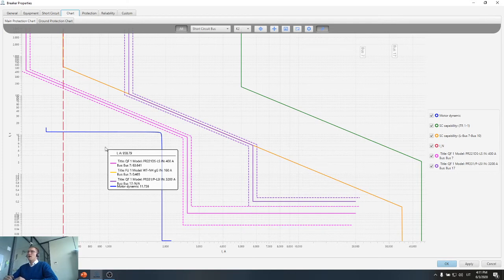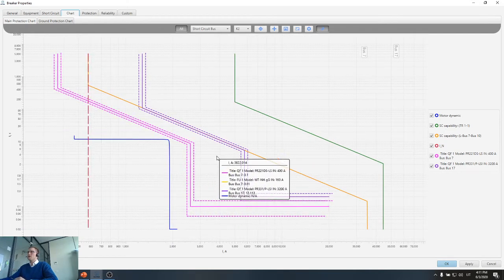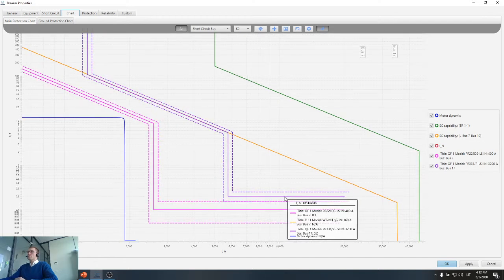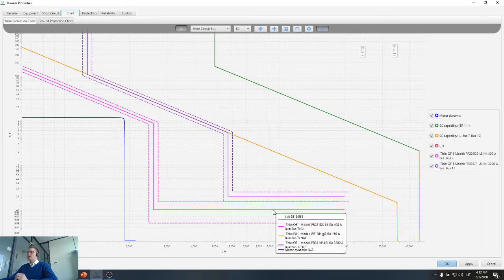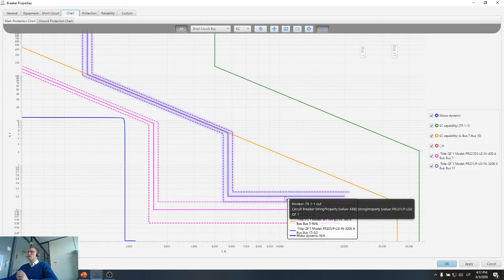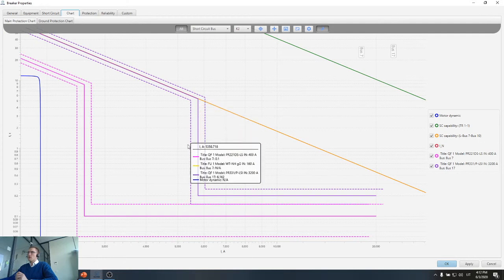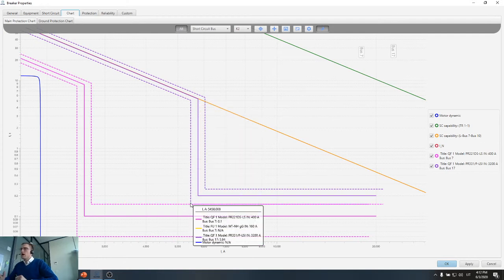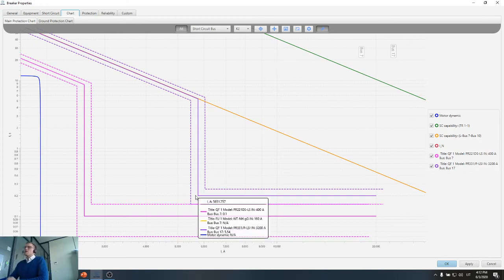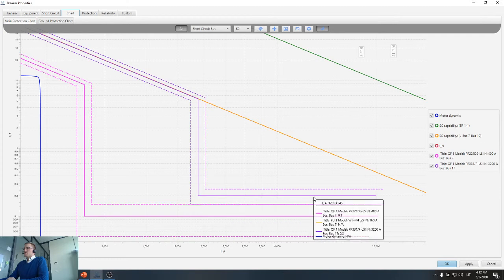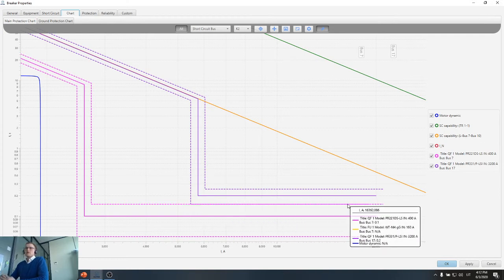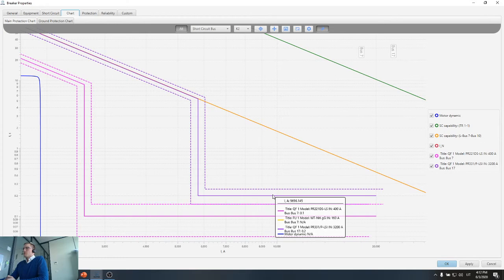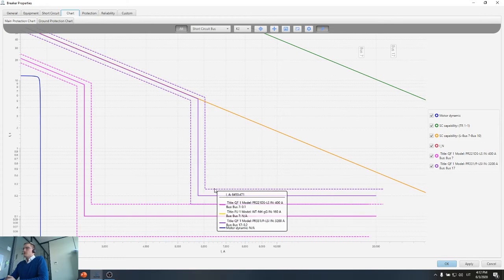But if you use the same manufacturer equipment, like the same manufacturer breakers, like in this case I have an ABB breaker and an ABB breaker here, then even a smaller time margin can be used, and in this case only 100 milliseconds is used. But in our software, what you should take into account is these dashed margin lines. They show the possible operation time margin for the breaker. So the breaker in theory should operate by this solid curve. However, no equipment is ideal, and it will operate with some error, so the time margin is provided by the dashed lines.